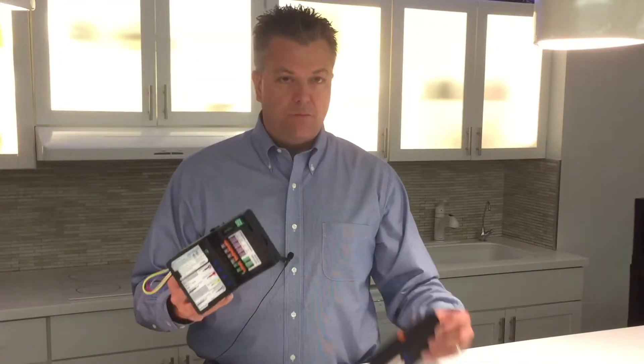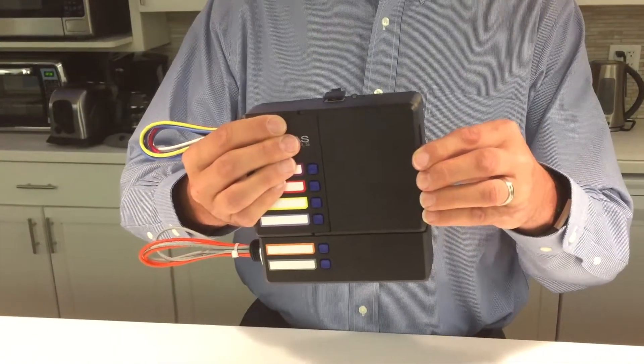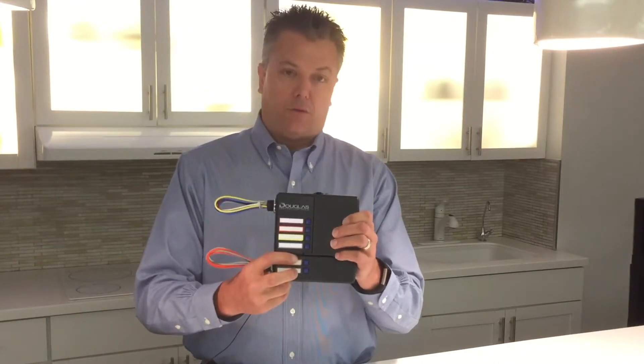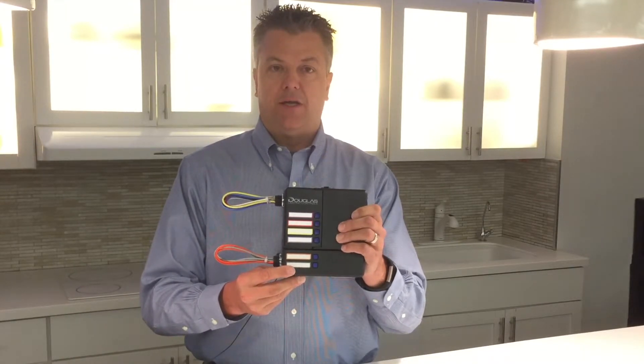As an option we can add a two-relay expansion pack that simply snaps into place. Each of the relays in the expansion pack is also a 20-amp load. These can be controlling normal lights, but it's also UL 924 listed, allowing you to control emergency lights.